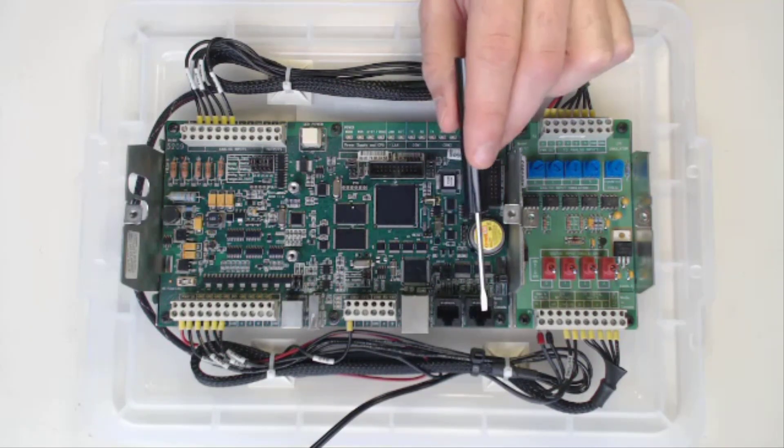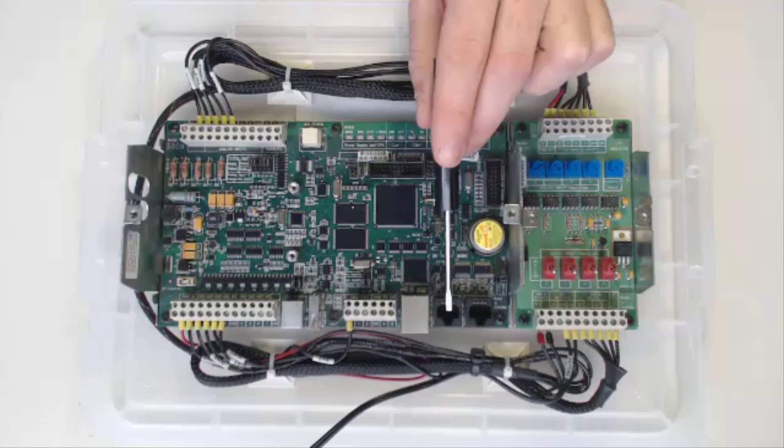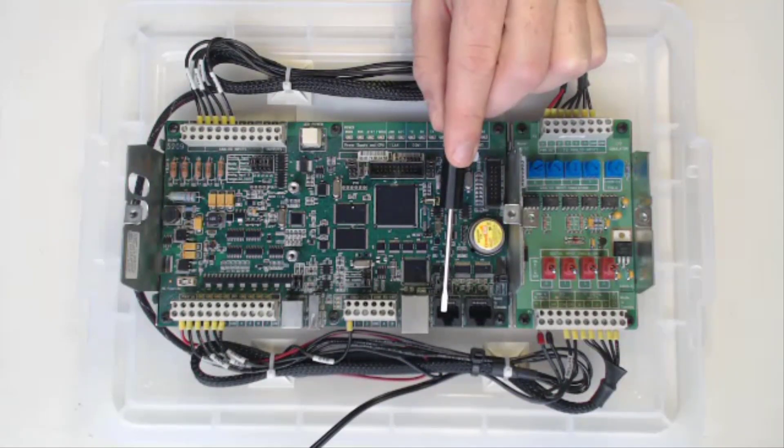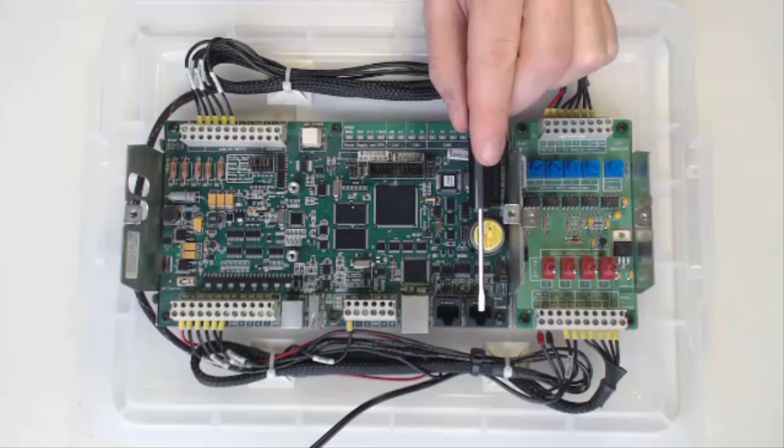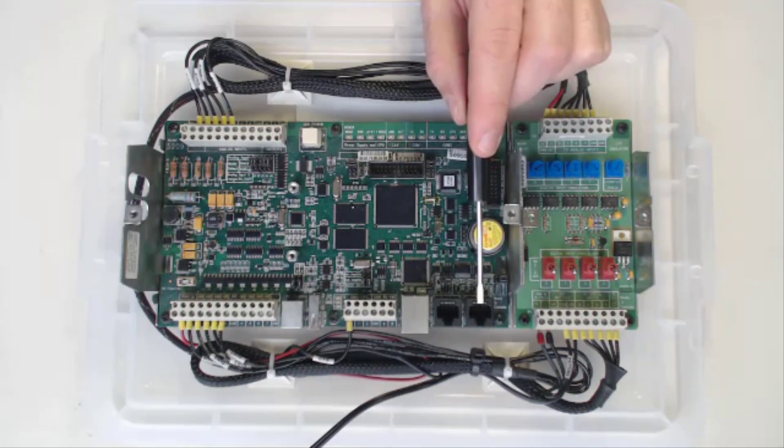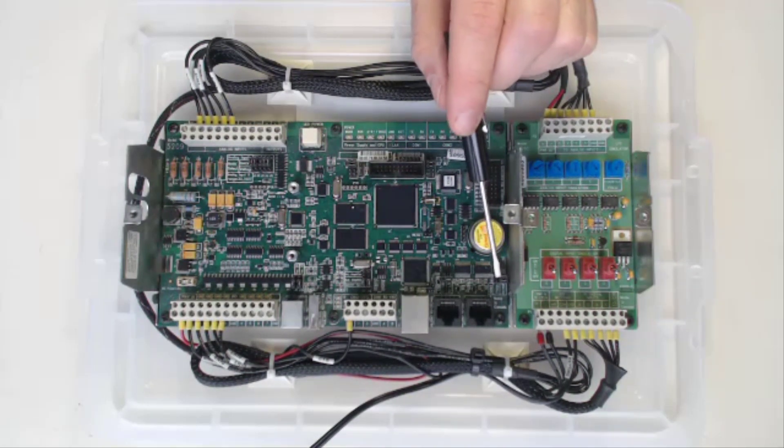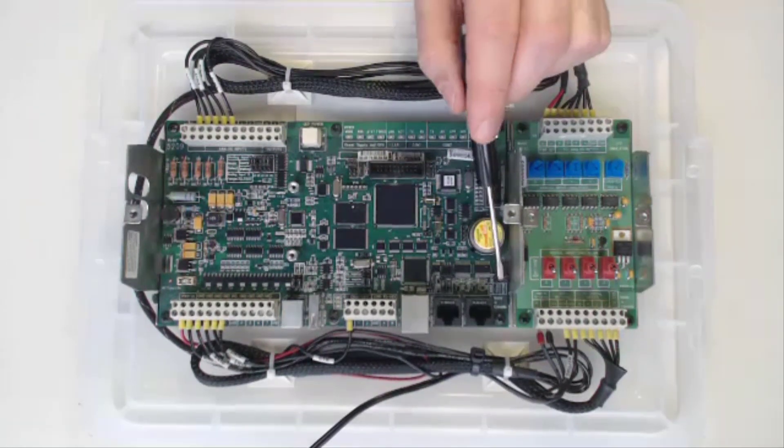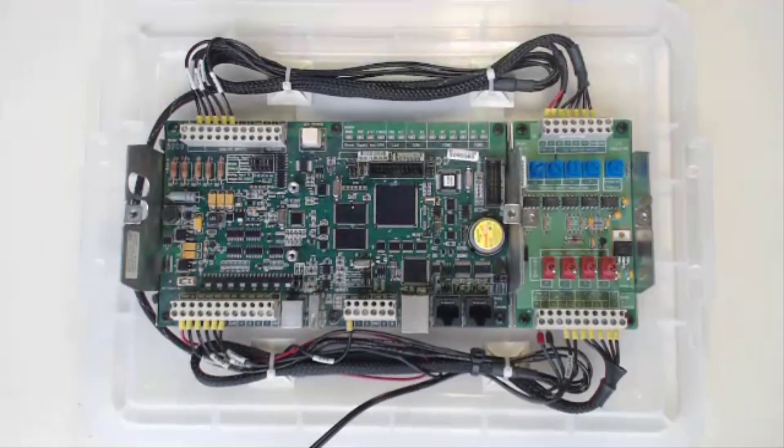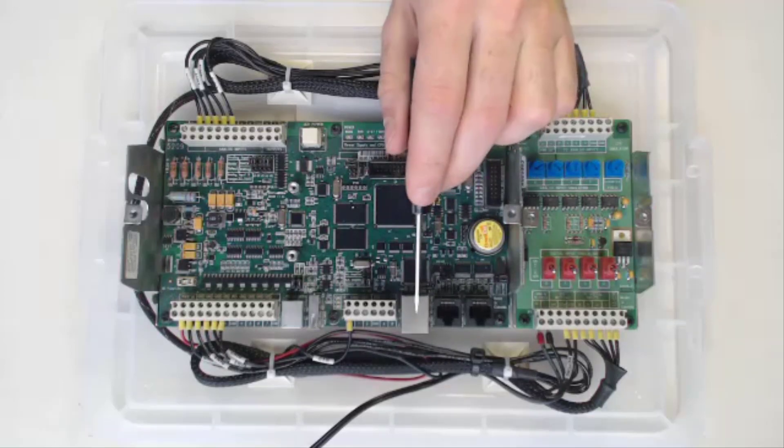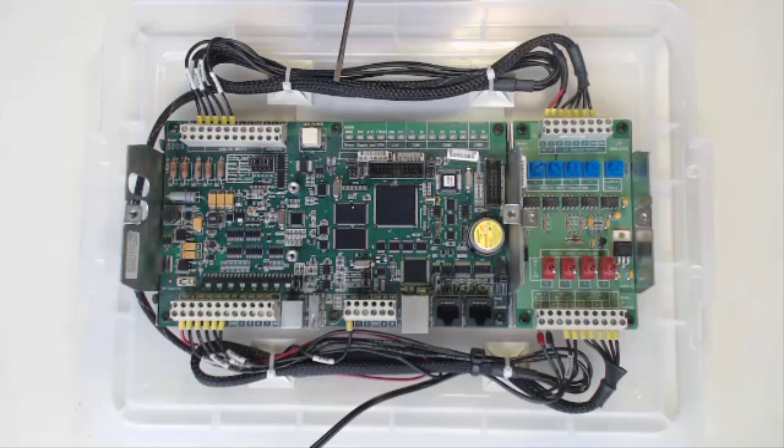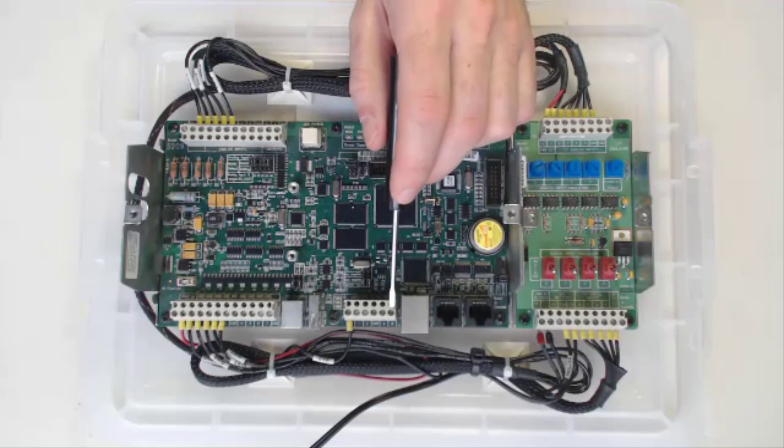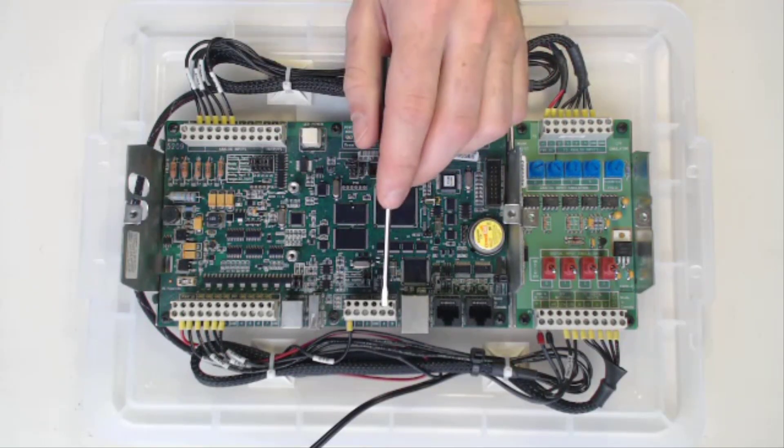Below that are two of your serial ports: COM2 and COM3, obviously the RJ45 ports. COM2 can be 232 or 485. There's dip switches here to change that. COM3 can only be 232. The one benefit of using COM3 is you can also power a 5-volt keypad display on COM3 as well. Next to that you have your metal RJ45 port here. That's your Ethernet or LAN port.